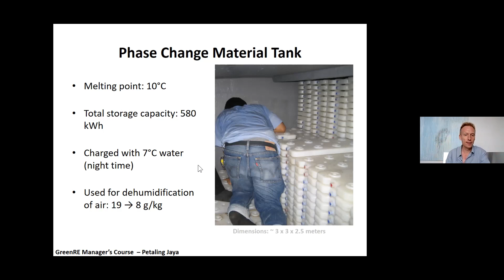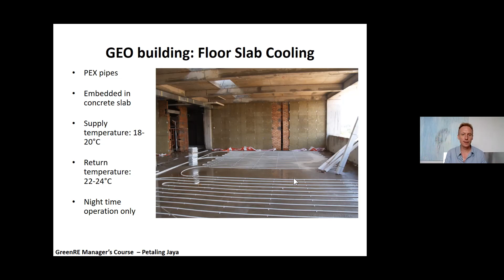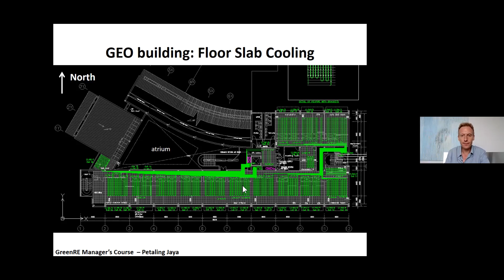For all the floors and ceilings, we had this floor slab cooling system, where pipes are laid, and on top of this there's a screed. They're embedded in the concrete slab, so every night we run in 18-degree water, cool down the whole floor to about 21 degrees or so, and this cooling is released passively to the spaces throughout the next day. So there's only about a 1 degree temperature swing of this whole thermal mass of the floors. It's quite an easy way to cool, and it's self-regulating, because if it suddenly becomes very hot, say a lot of sun comes in, the temperature difference increases, and therefore more cooling is given off. Here you can see how the pipes are laid.